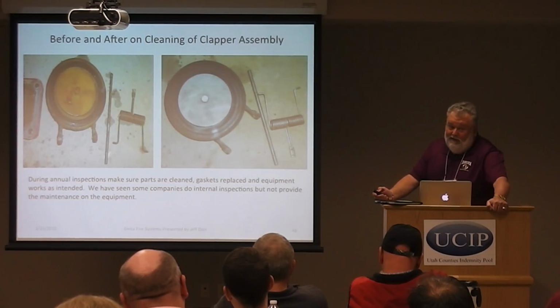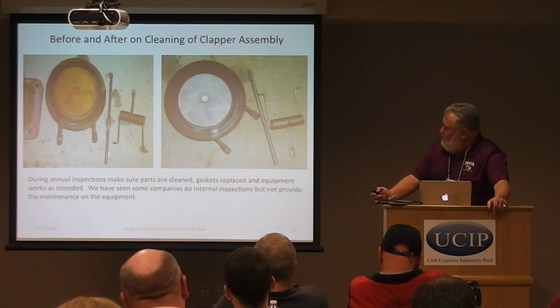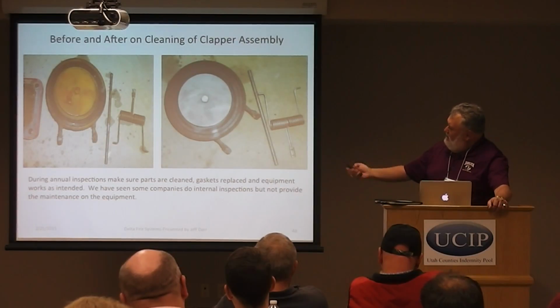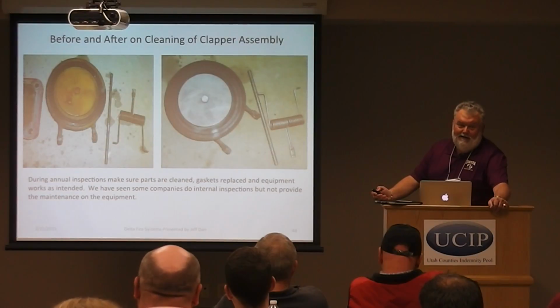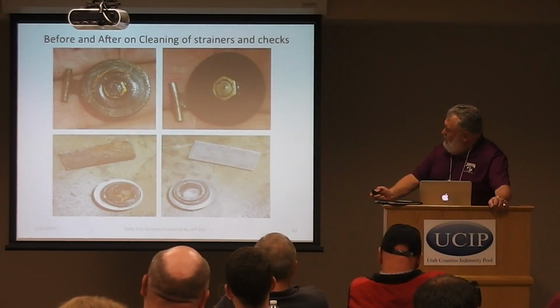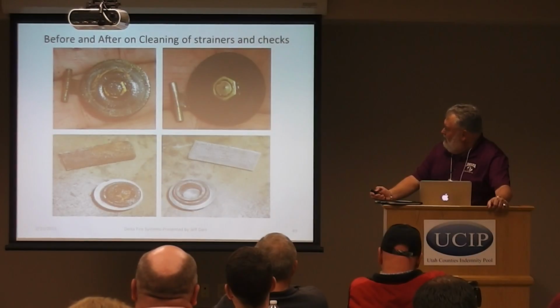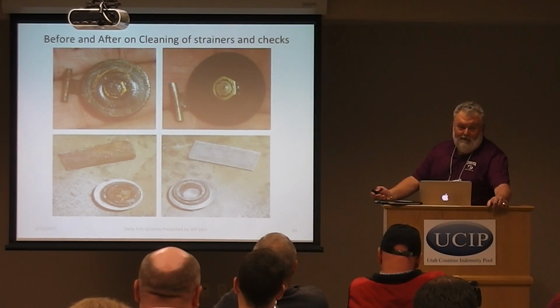And when we do the internal inspections on valves, some customers want to do their cleaning and maintenance themselves, and if that's what you prefer, we can do that. But I just recommend that if we're there with our professional guys, just have us do the cleaning at that point in time. This is before and after on the clapper after we've cleaned it. The top one's a small check valve clapper. We replaced the gasket. You can see the strainer on the bottom. It's pretty well plugged up on the left. Again, we clean it, make sure it's operating correctly before we leave the site for you.